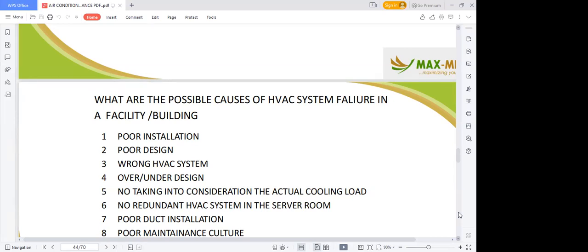And every rule of thumb does not take into consideration what needs to be cooled. A building in Lagos is different from a building in Maiduguri. Please take note. Don't use the design in Lagos for the design in Abuja or Port Harcourt. They might be the same building with the same number of people, but the environmental conditions of the building vary. So that's why sometimes you engage experts to do what they call a cooling load calculation before you decide. And the type of system you choose also has a direct impact on your budget or the comfort of the building.